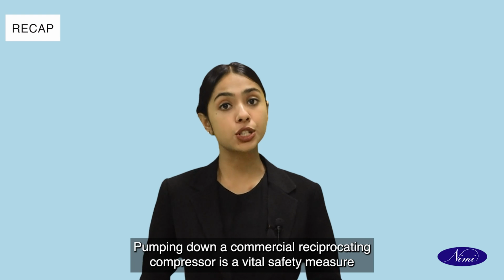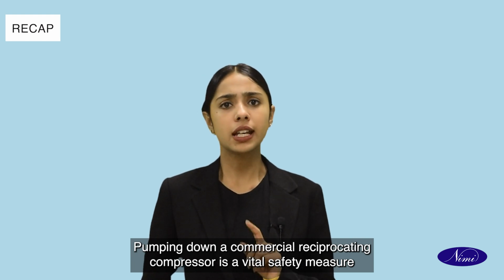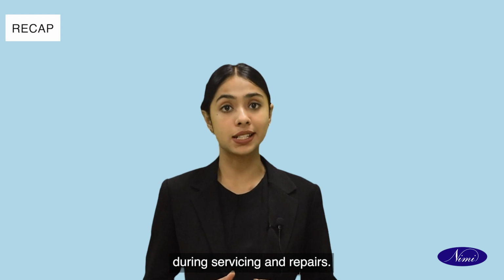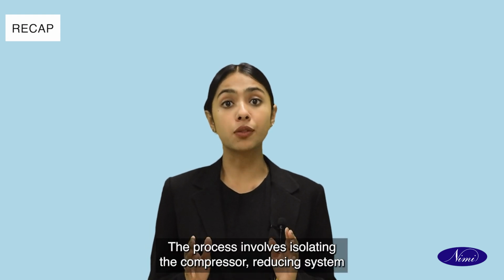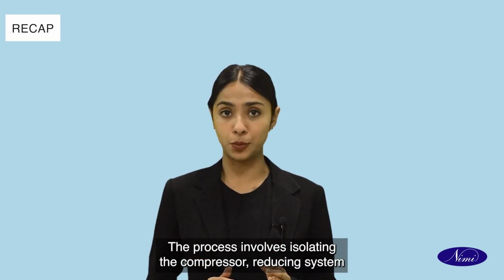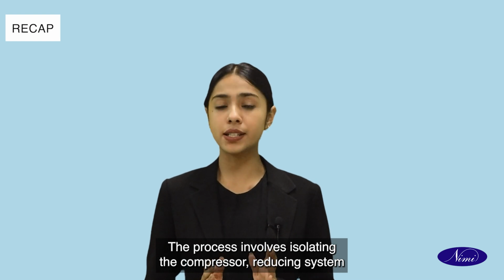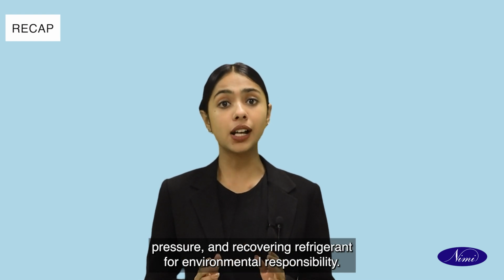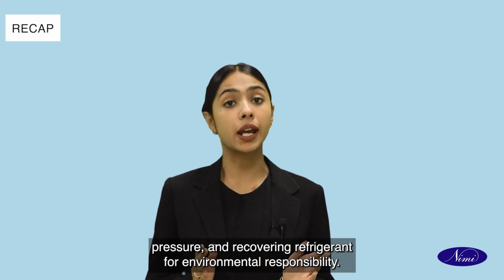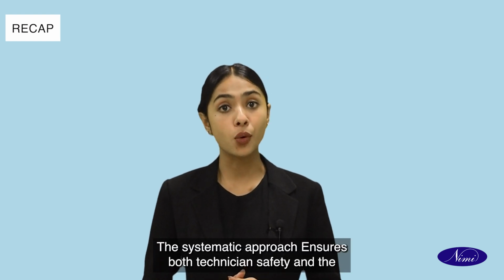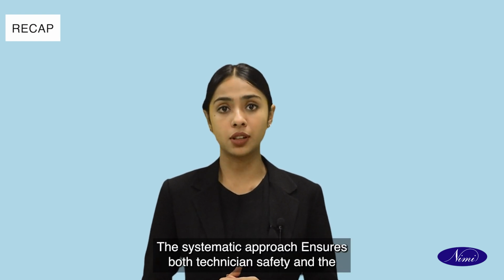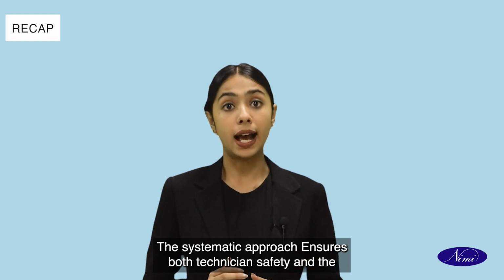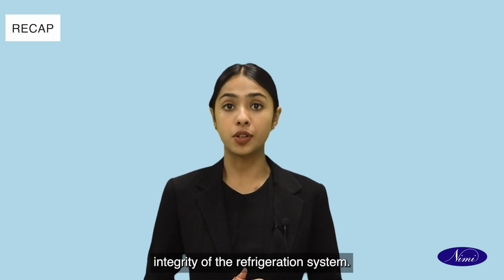Pumping down a commercial reciprocating compressor is a vital safety measure during servicing and repairs. The process involves isolating the compressor, reducing system pressure, and recovering refrigerant for environmental responsibility. This systematic approach ensures both technician safety and the integrity of the refrigeration system.